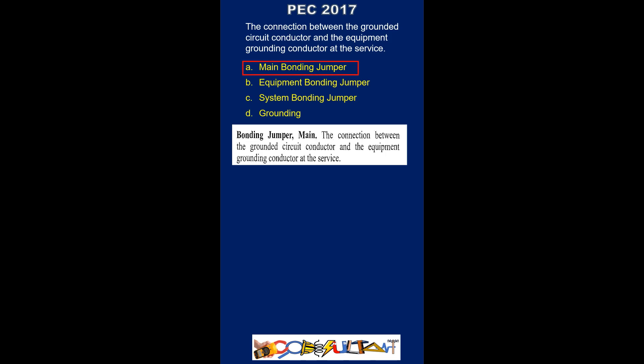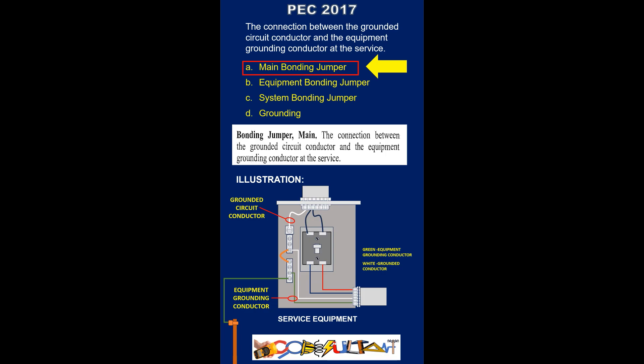Based on the code definition in Article 1, the main bonding jumper is the connection between the grounded circuit conductor and the equipment grounding conductor at the service. Therefore, the answer is letter A. The bonding jumper that links the equipment ground bus and the neutral bus serves as an example of a main bonding jumper, as shown in the illustration.